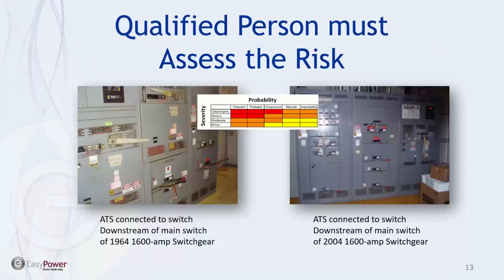Okay, so let's take a look at a couple of scenarios. The qualified person has to assess the risk, and so we've got a 1964 switchgear that's got an ATS connected to it, and we're going to work on the ATS. So this is both identical equipment. They're both 1600 amps. They're both 480 volts. So they're identical. The only thing that's different is this one's 1964 and this one's 2004. So at first glance, you think, I'd rather work on the 2004 switchgear. It's probably going to be safer than the 64 switchgear.